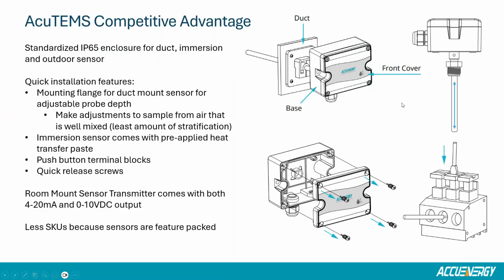We have the flexibility of the adjustable flange with the duct mount unit, and preloaded heat transfer paste in the immersion sensor. Here's a visual - the screws are disconnected from the enclosure, but I assure you these screws are self-capturing, so the installer isn't going to lose them in the field. It's essentially a quarter-turn spring-loaded self-capture screw. You turn the four screws and the enclosure cover pops right off. We also have push button terminal blocks instead of the multi-turn screw terminal blocks.